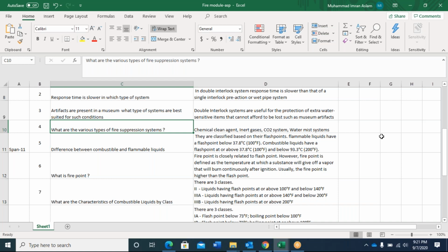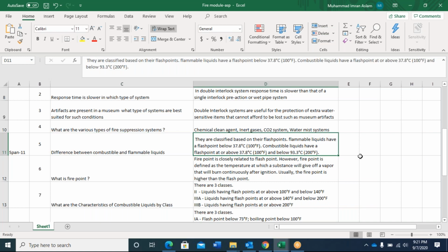The next question is the difference between combustible and flammable liquids. They are classified based on their flash points. Flammable liquids have a flash point below 37.8 degrees Celsius or 100 degrees Fahrenheit. Usually in the book it's given as 100 degrees Fahrenheit; I noted 37.8 degrees Celsius for my own easy remembrance, just to understand how room temperature usually works in our place, so that's easy for me to remember. The next one is combustible liquids, which have a flash point at or above 100 degrees Fahrenheit and below 200 degrees Fahrenheit.